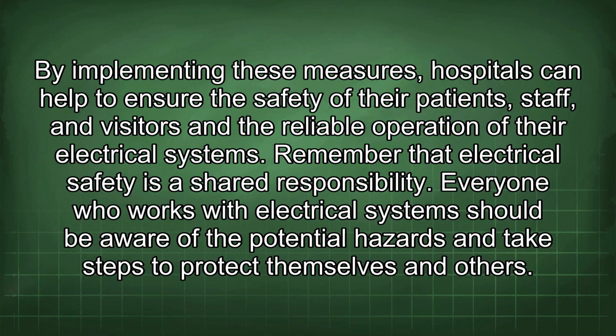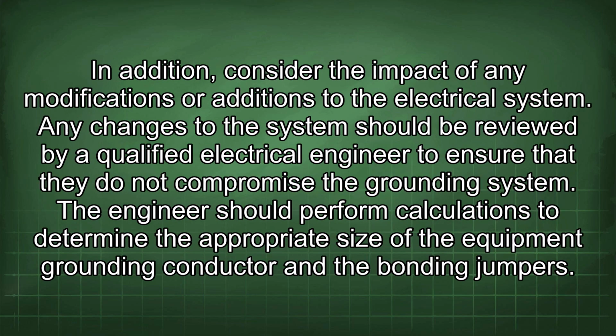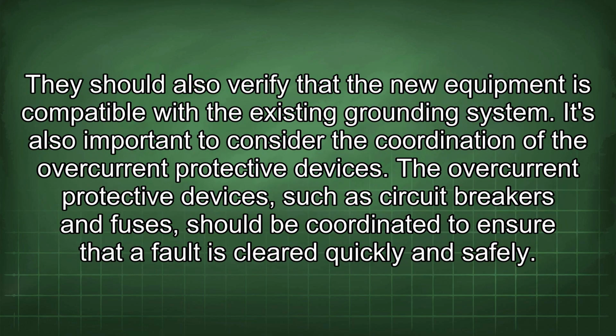Remember that electrical safety is a shared responsibility. Everyone who works with electrical systems should be aware of the potential hazards and take steps to protect themselves and others. In addition, consider the impact of any modifications or additions to the electrical system. Any changes to the system should be reviewed by a qualified electrical engineer to ensure that they do not compromise the grounding system. The engineer should perform calculations to determine the appropriate size of the equipment grounding conductor and the bonding jumpers. They should also verify that the new equipment is compatible with the existing grounding system.